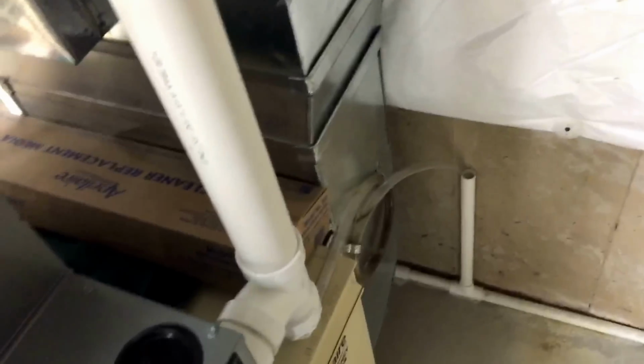Okay, that's to check your static pressure drop across your filter, and then right here to see what your total static pressure is of the unit when you install it. The guys aren't drilling holes. I'm not saying that you totally have to drill holes in the furnace. I did this one here because that's just the way to test it for me. But they should be doing proper testing when they start this equipment up.